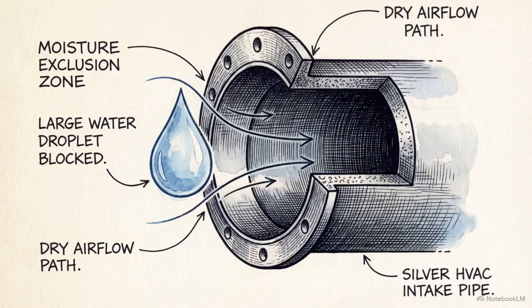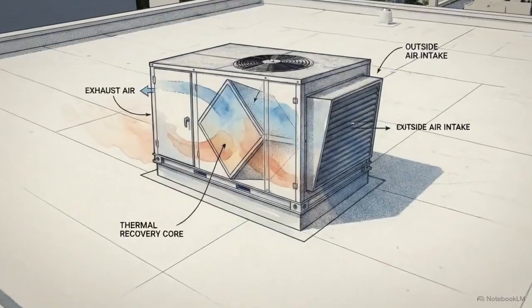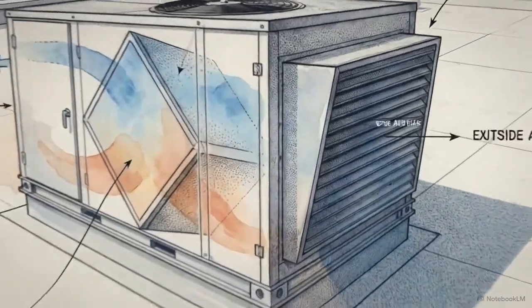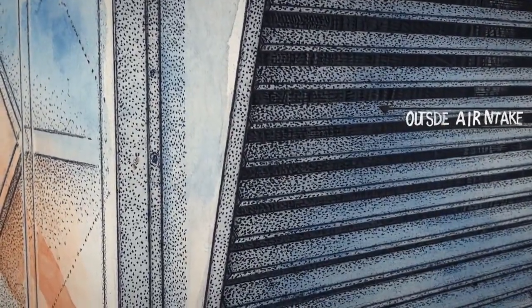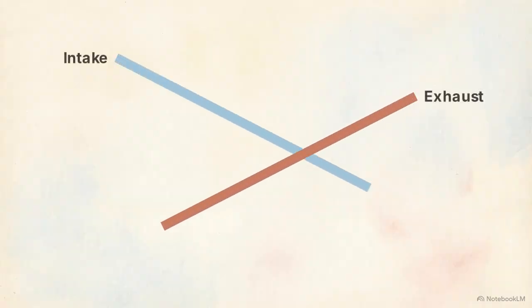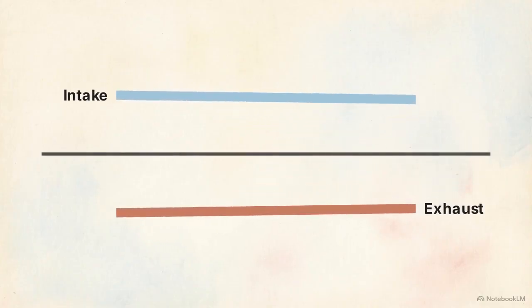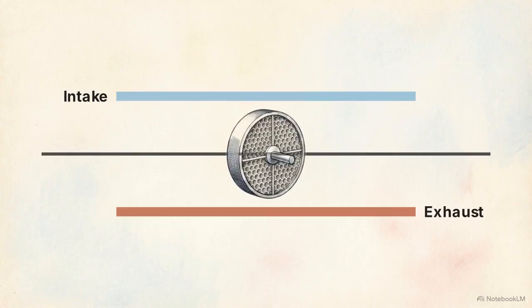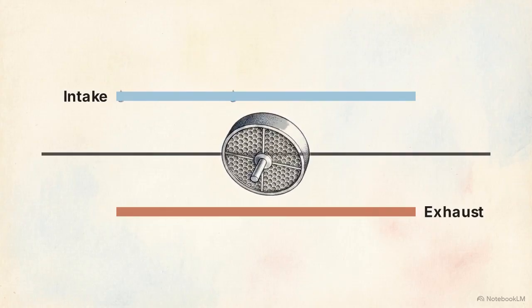Active reheating solves the indoor air, but to make the system efficient, we must reduce the latent load before it ever reaches the cooling coil. The enthalpy recovery ventilator, or ERV, acts as the mechanical gatekeeper for all fresh air entering the building. An ERV is a system that exchanges stale indoor air for fresh outdoor air, while transferring heat and moisture between the two streams. This diagram shows the physical mechanism inside an ERV.